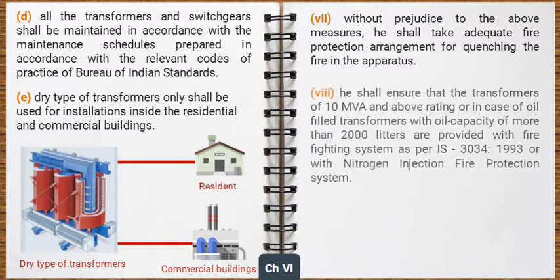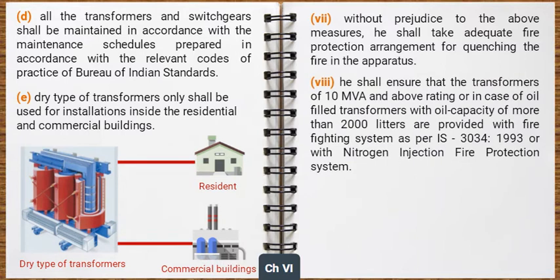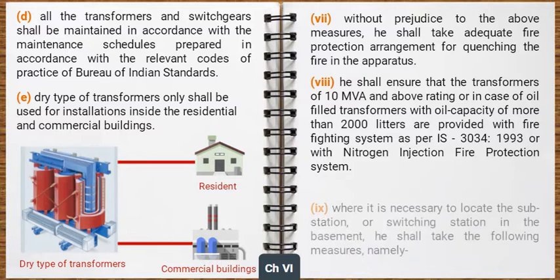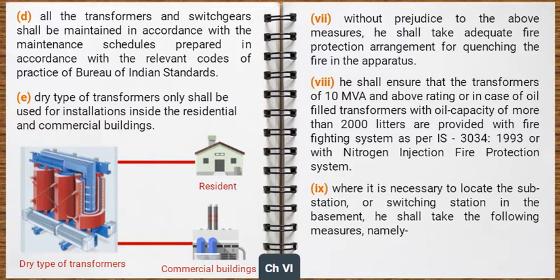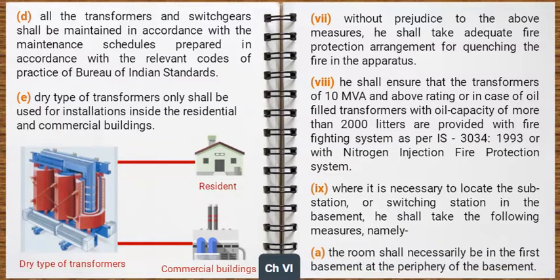He shall ensure that the transformers of 10 megavolt ampere and above rating, or in case of oil-filled transformers with oil capacity of more than 2000 liters, are provided with firefighting system as per IS 3034-1993 or with nitrogen injection fire protection system. Where it is necessary to locate the substation or switching station in the basement, he shall take the following measures, namely: the room shall necessarily be in the first basement at the periphery of the basement.